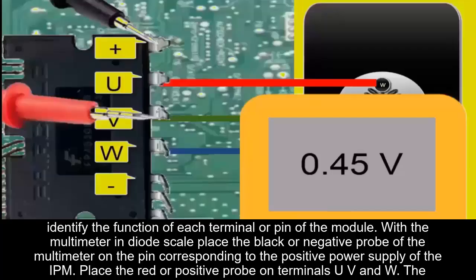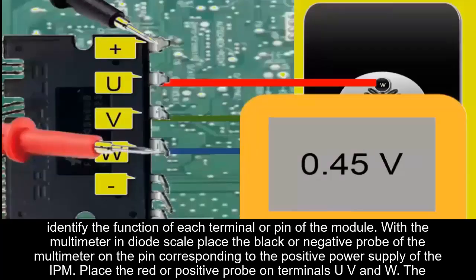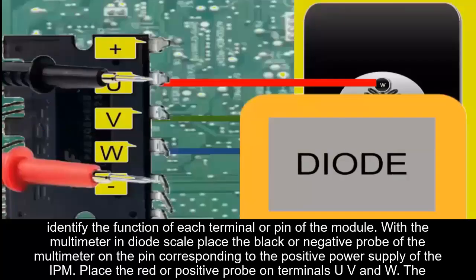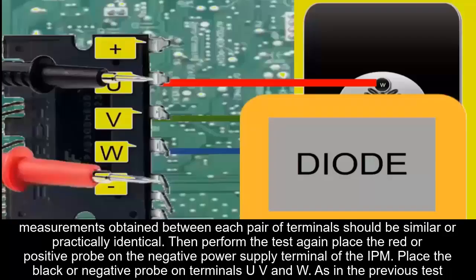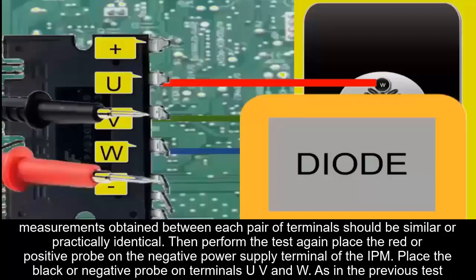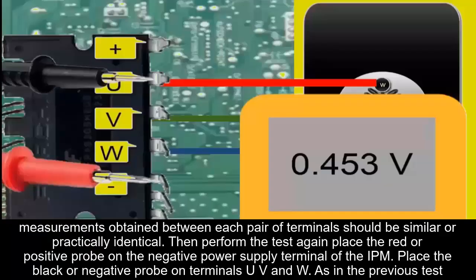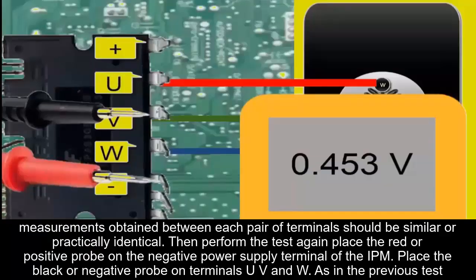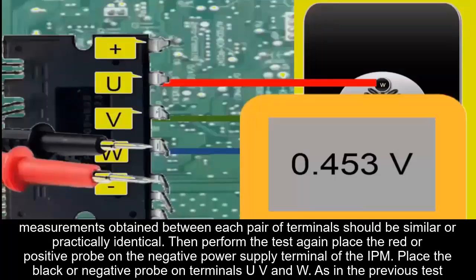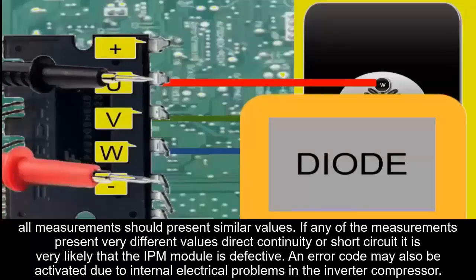Place the red or positive probe on terminals U, V, and W. The measurements obtained between each pair of terminals should be similar or practically identical. Then perform the test again. Place the red or positive probe on the negative power supply terminal of the IPM, and place the black or negative probe on terminals U, V, and W. As in the previous test, all measurements should present similar values.